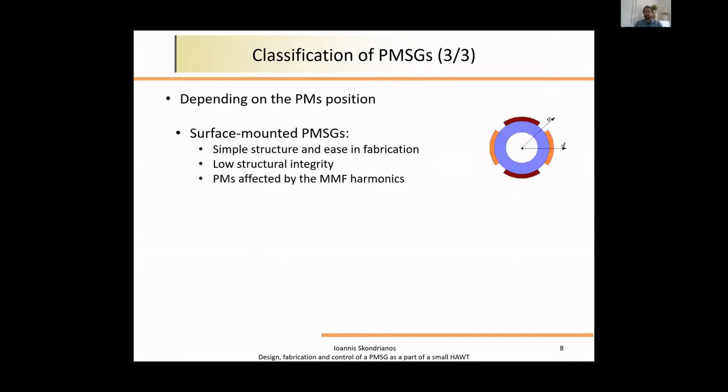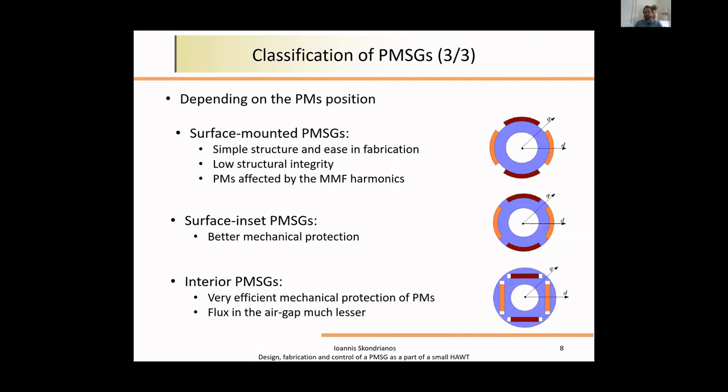Depending on magnet position, magnets located on the rotor, we have three configurations. Surface mounted magnets, characterized by simple structure and ease in fabrication. However, they have low structural integrity, especially at very high rotational speeds, and are affected by magnetomotive harmonics. Second is surface inset PMSGs in the rotor with better mechanical protection. The best mechanical protection is given by interior PMSGs, most efficient in structural integrity, but the flux in the air gap they produce is much lesser.